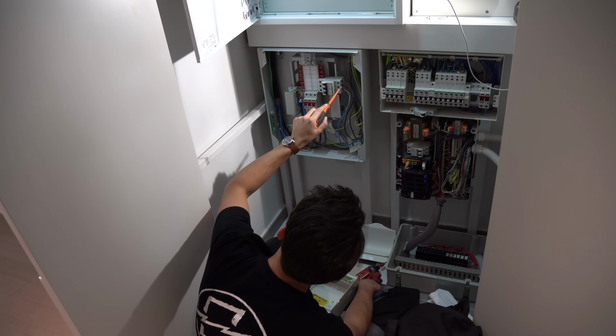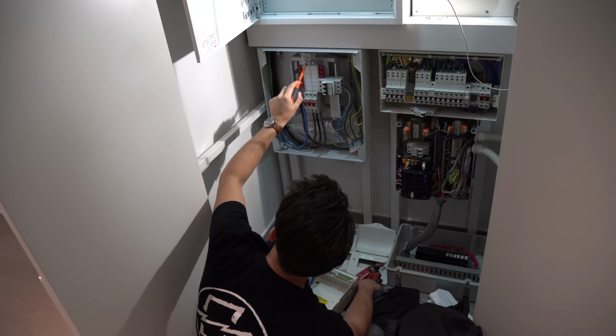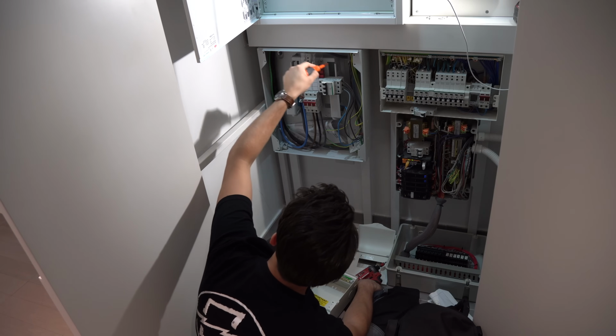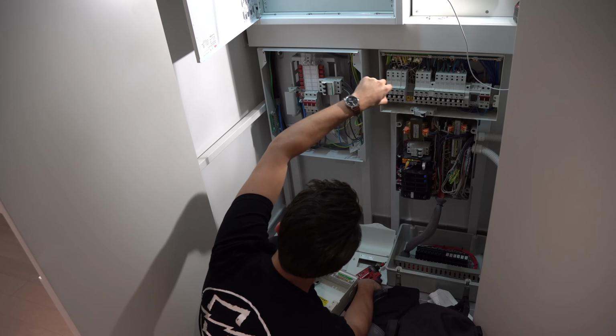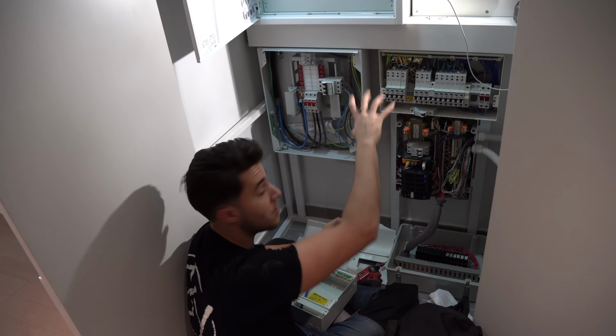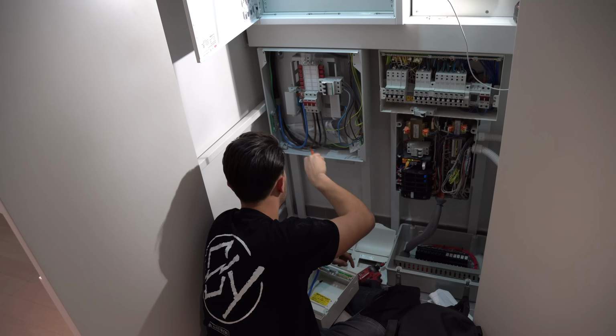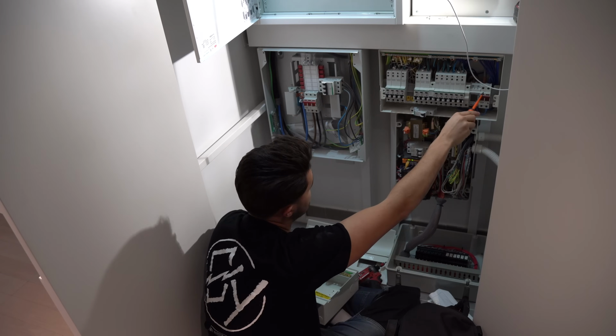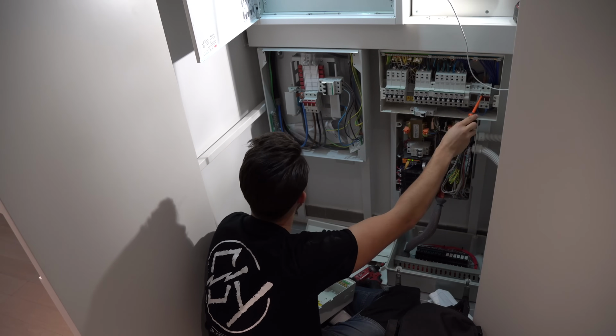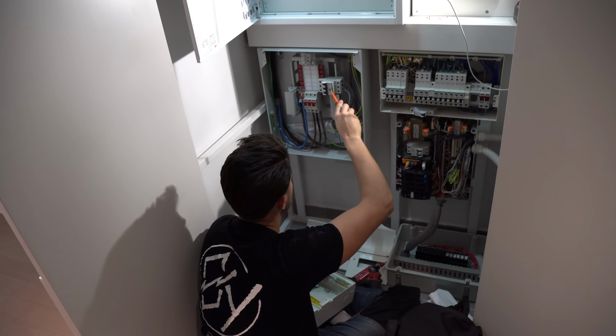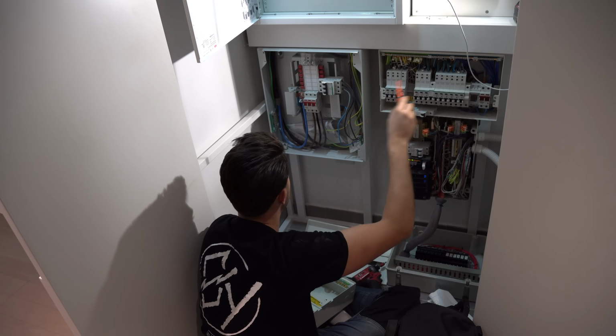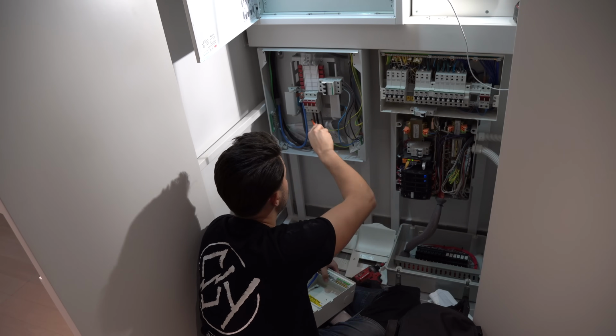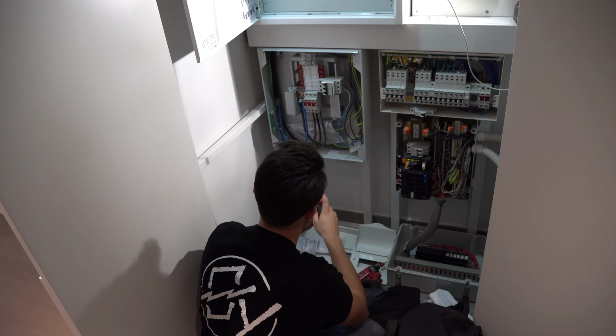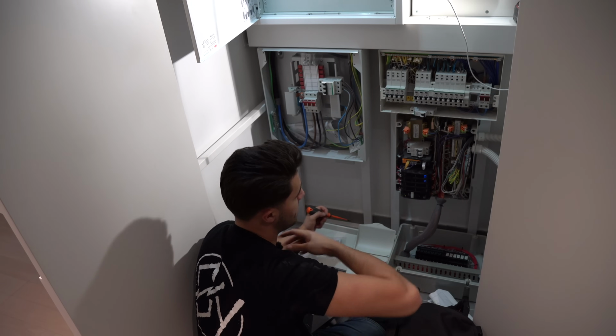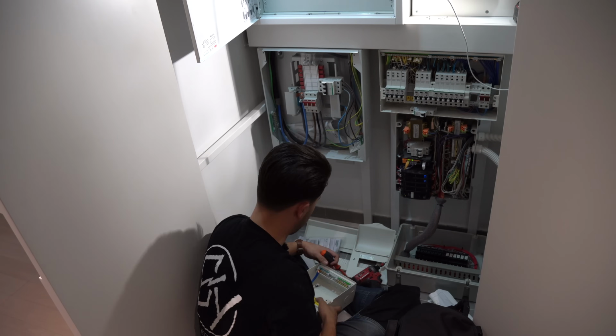So you've got this here, which is the D20, which is going off. And then you've got this supply here going out to this single phase distribution board, because most of this house is just three phase loads. The neutral for that comes out there and goes off to this little chamber here. So I can't actually isolate this board from here. If I want to isolate the top of this main switch, I'll have to isolate it from here, and I'm not able to isolate this. I'll have to go to probably some kind of switchboard or riser room somewhere to get to that.